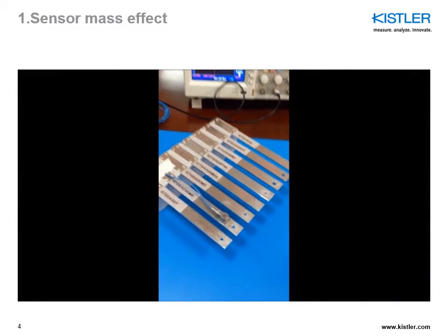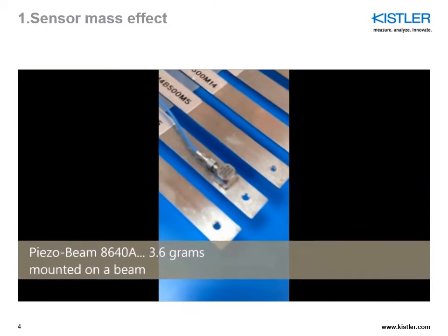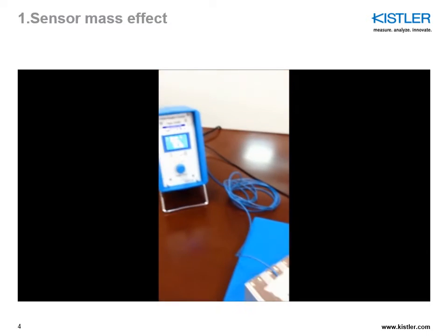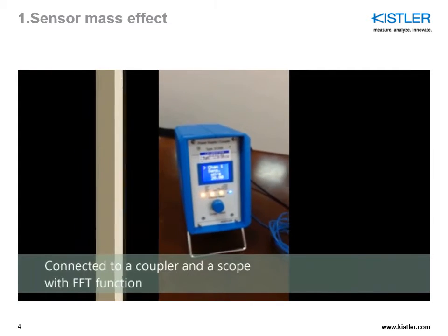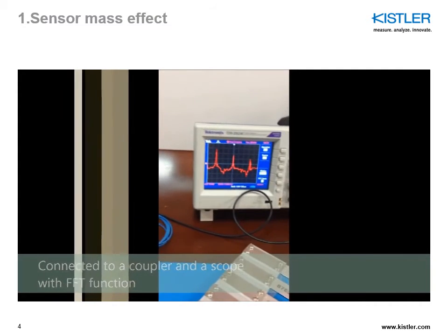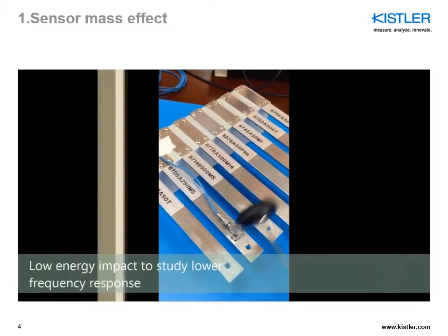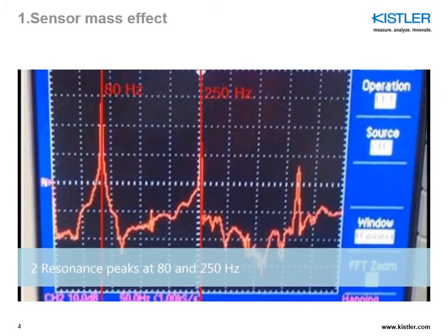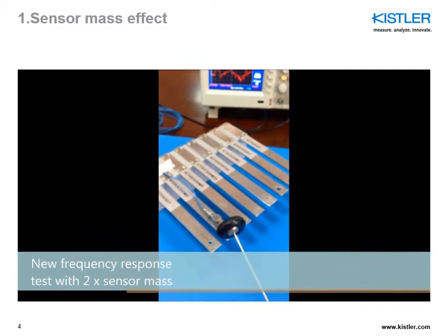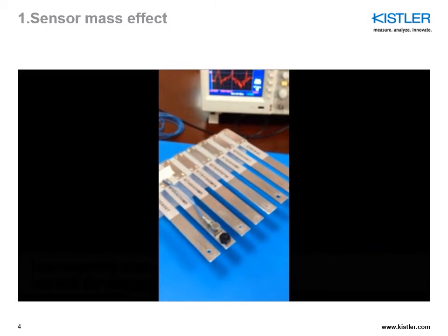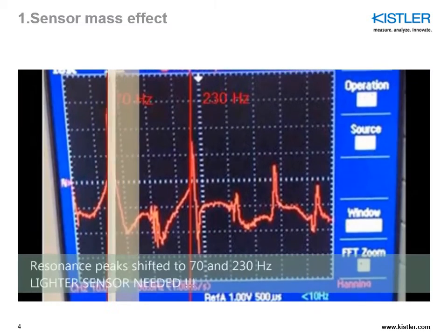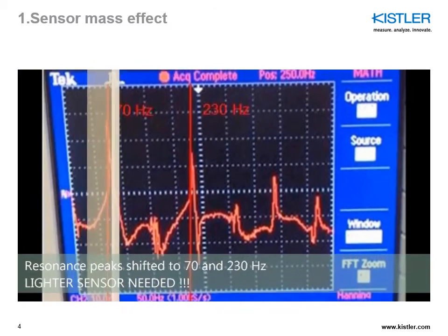We are here performing a very simple test using a cantilever beam demo setup. We are mounting one of our piezo beam 8640A sensors, which is 3.6 grams — not really negligible compared to the mass of the beam. We perform a shock test to excite resonance and look at the first two resonance peaks showing up at 80 Hz and 250 Hz. We then mount an additional mass comparable to the sensor mass and the two peaks shift down to 70 Hz and 230 Hz.